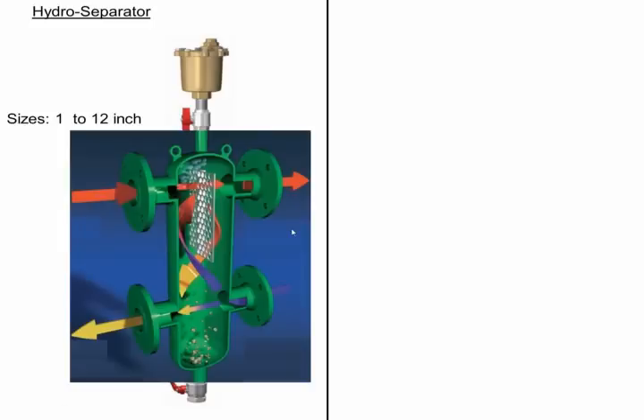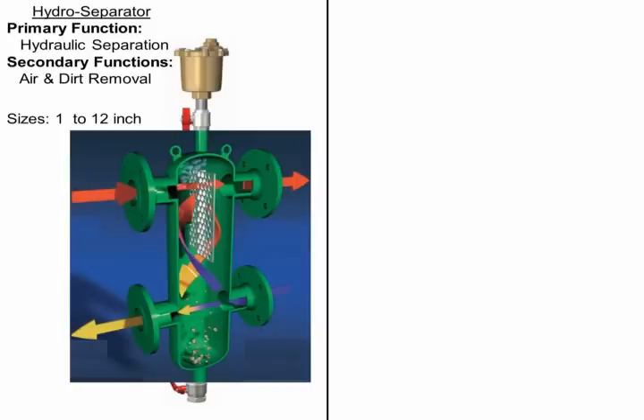It takes what otherwise would be turbulent flow and makes it laminar. Turbulence equals pressure drop, which is what we don't want. We want to make it laminar. Furthermore, the baffle plate has been perforated, and that creates that sharp edge effect we talked about. So we get coalescing here, and we get air coming out of solution, or microbubbles getting pulled out and vented out. So we get some air separation here, and we get some dirt separation here. So the primary function of a hydraulic separator is to decouple pumps, that is, hydraulic separation. Secondary functions are air and dirt.